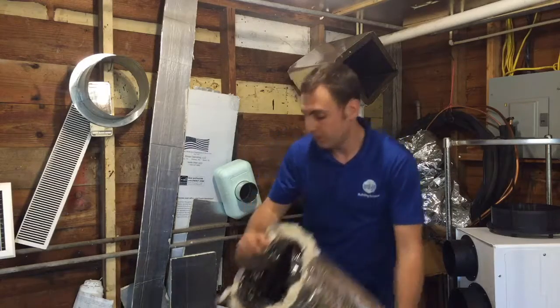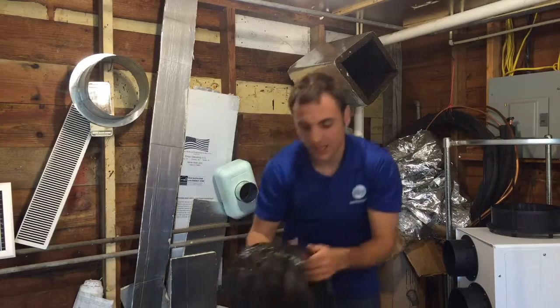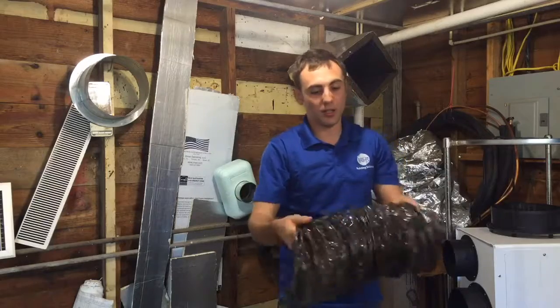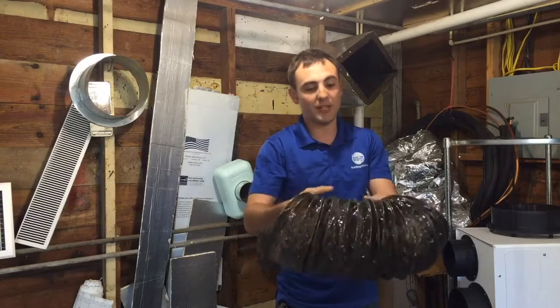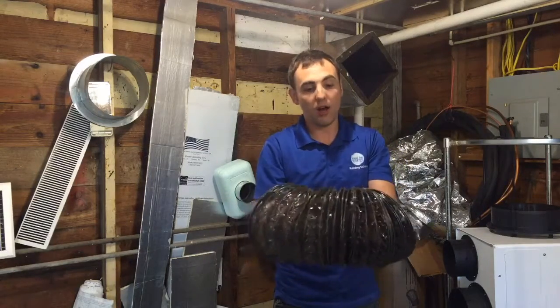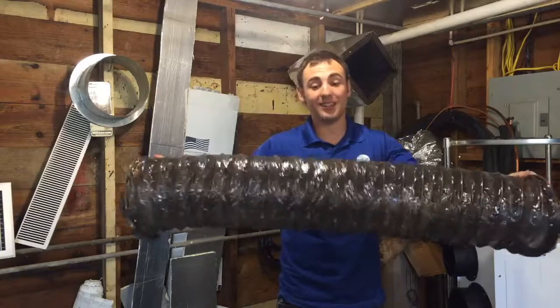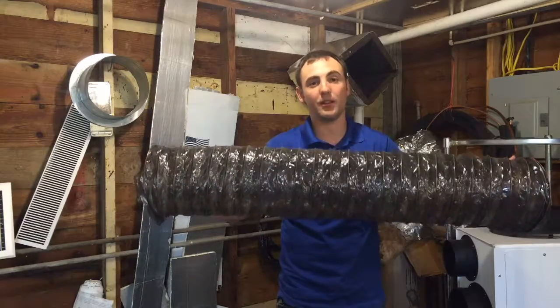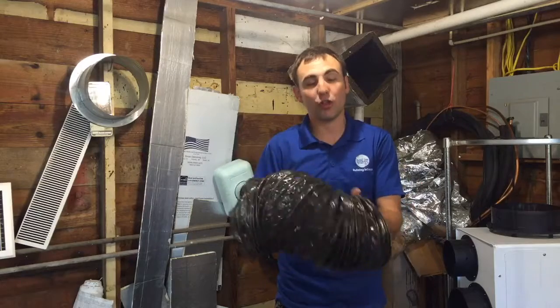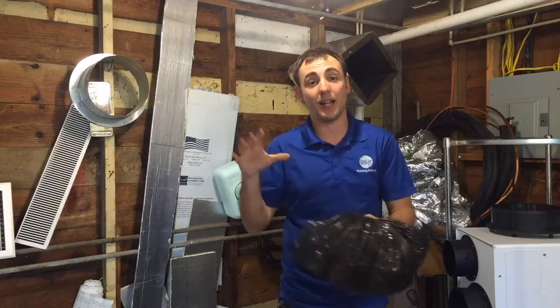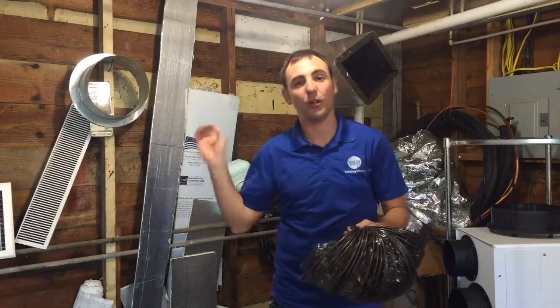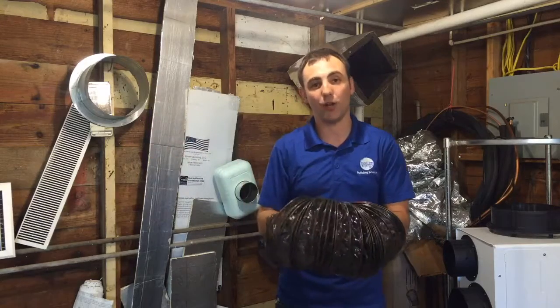So you can see with flex duct, it's very flexible. And you can see it's got these ridges in it, and obviously you want to stretch this as tight as possible because you want the least amount of friction to be created inside, basically a way for the air to slow down. You want to be able to have a smooth path for that air to go through.